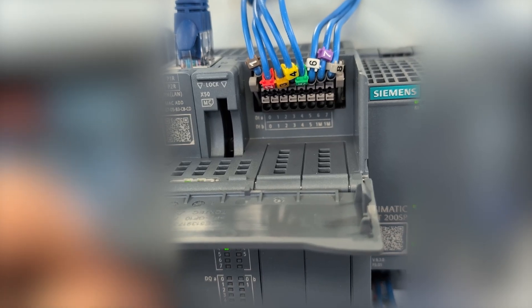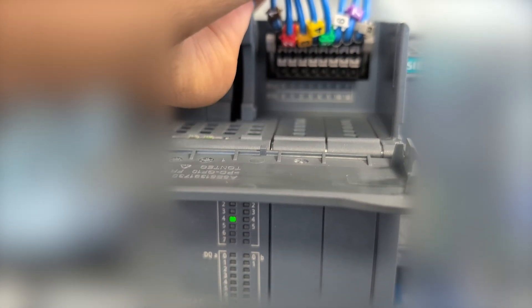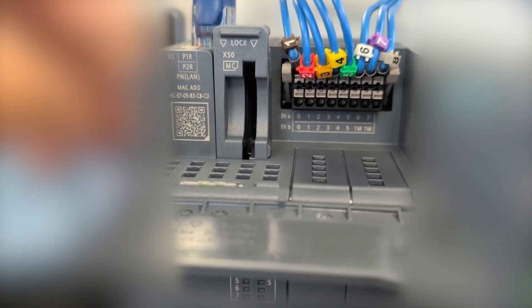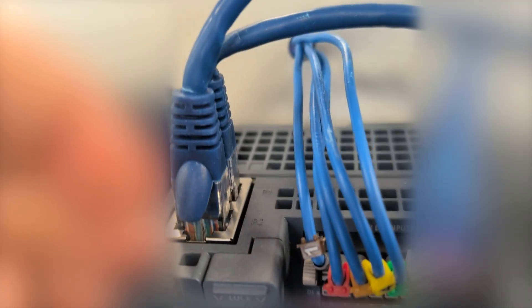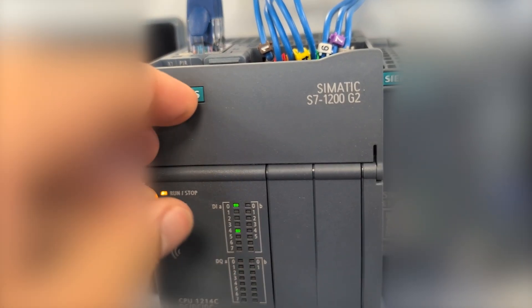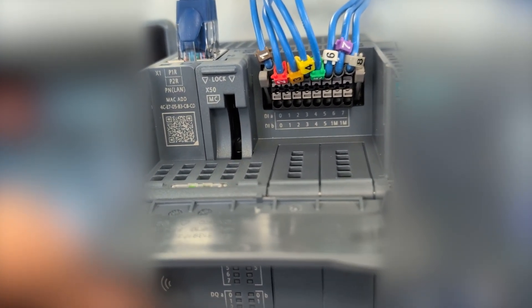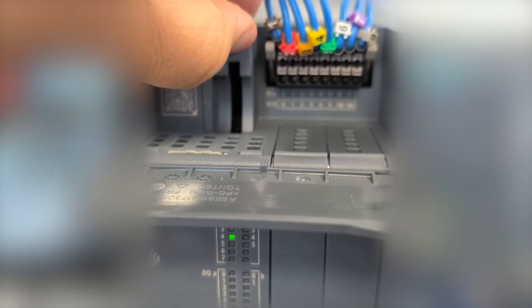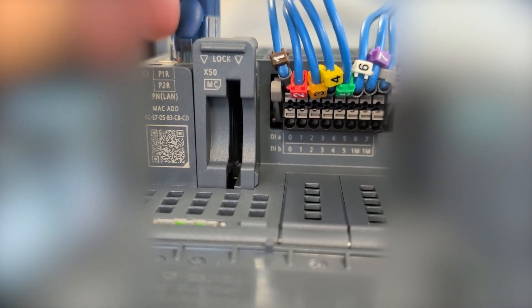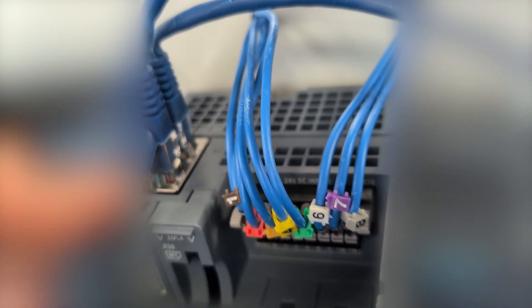The two Ethernet ports are huge. That was a huge thing for me because I don't have space and I don't want to be putting network switches on everything. So the fact that they come with two Ethernet ports instead of the original 1200, which only has one, that was huge for me. And yeah, it sucks that I'm not going to be able to use that feature. What was weird, though, is that the Ethernet ports are on top and I don't get that because they've got a power connector at the bottom, which I love. I love the power connector that they're using on this new G2. But the Ethernet ports are on top. So if I've got an ET200 SP next to it, which I do have, I've got to go from Ethernet cable out the top of the 1200 and I've got to go through my panel and then back around to get to the bottom of my ET200 SP. It's just like, the ET200 SP Ethernet ports are on the bottom. The old 1200 Ethernet ports are on the bottom. The 1500 Ethernet ports are on the bottom. Why is it now top entry? Yeah, it's a bit weird. But two Ethernet ports is huge.